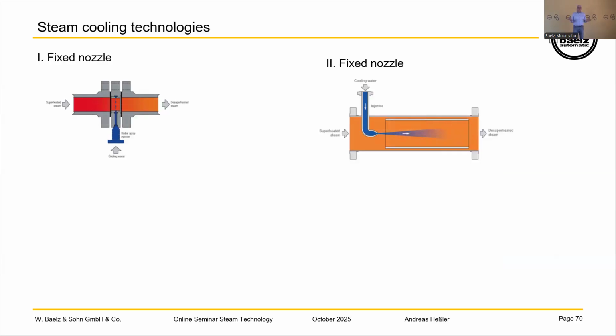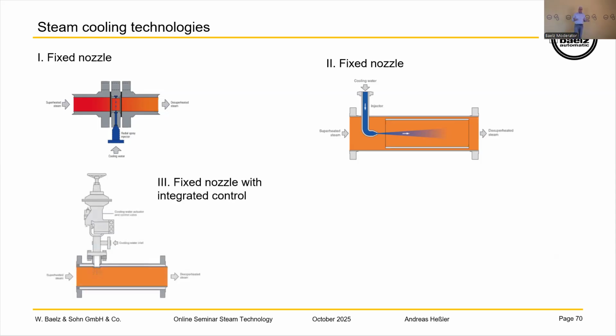Steam cooling technologies. What we can do is a fixed nozzle in two different ways. Here we see it as a ring, or just spray it over inside of the steam. The next one we can do is a fixed nozzle with an integrated control, so you do not have to use an extra control valve to control the water flow.